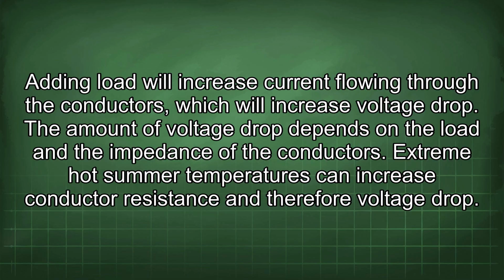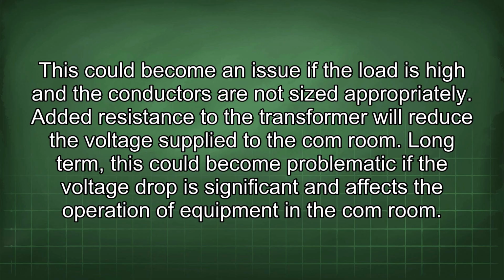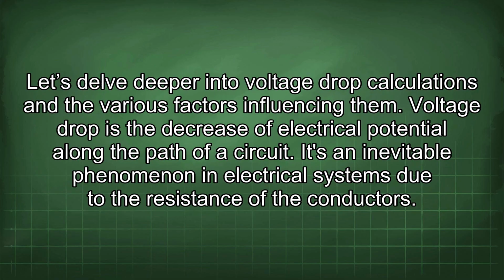The amount of voltage drop depends on the load and the impedance of the conductors. Extreme hot summer temperatures can increase conductor resistance and therefore voltage drop. This could become an issue if the load is high and the conductors are not sized appropriately. Added resistance to the transformer will reduce the voltage supply to the comm room. Long term, this could become problematic if the voltage drop is significant and affects the operation of equipment in the comm room. Let's delve deeper into voltage drop calculations and the various factors influencing them.